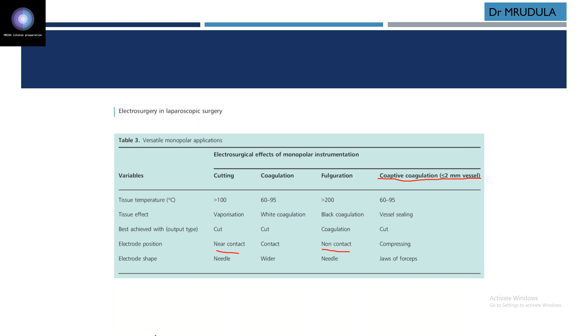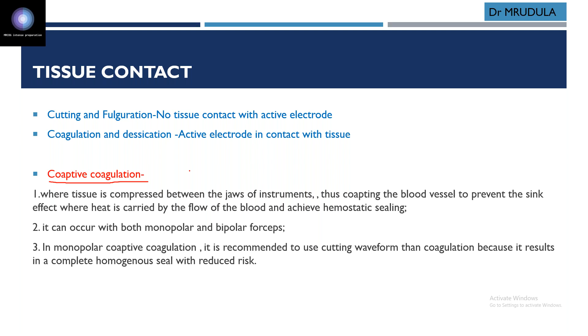Tissue contact, as I told you: in cutting and fulguration there is no tissue contact, while in coagulation and desiccation there will be active contact with the tissue. This is the coaptive coagulation I just explained. The tissue is compressed between the jaws of the instrument, coapting the blood vessels to prevent the heat sink effect, where heat is carried away by the flow of blood, and achieve hemostatic sealing. It can occur with both monopolar and bipolar forceps. In monopolar coaptive coagulation, it is recommended to use the cutting waveform rather than coagulation because it results in a complete, homogeneous seal with reduced risk. So basically you stop the blood flow between the two jaws so that no blood flows through that vessel.